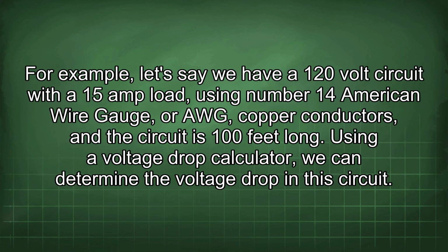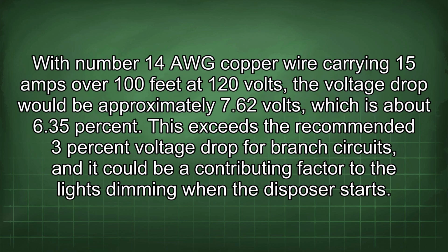For example, let's say we have a 120 volt circuit with a 15 amp load, using number 14 American Wire Gauge, or AWG, copper conductors, and the circuit is 100 feet long. Using a voltage drop calculator, we can determine the voltage drop in this circuit. With number 14 AWG copper wire carrying 15 amps over 100 feet at 120 volts, the voltage drop would be approximately 7.62 volts, which is about 6.35%.